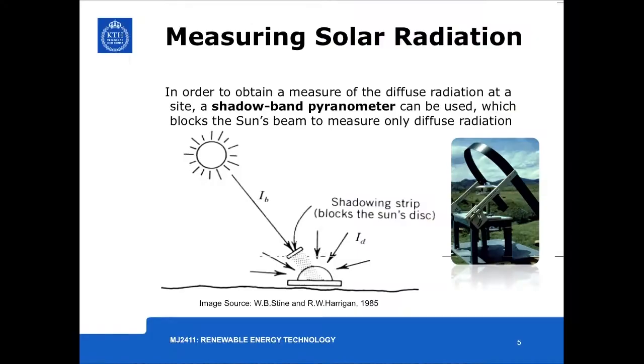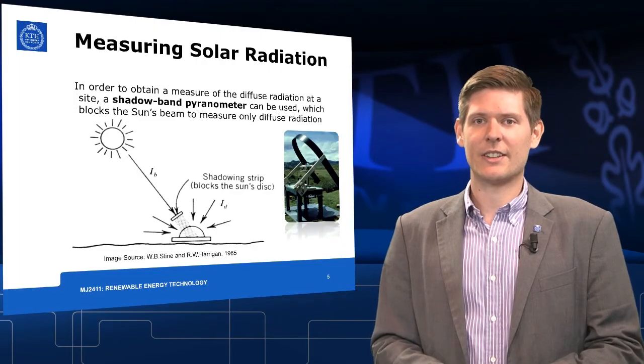In order to obtain the diffuse radiation, we need to modify a pyranometer. In order to measure the diffuse radiation, we attach a shadow band to a pyranometer, which allows us to measure the diffuse radiation.